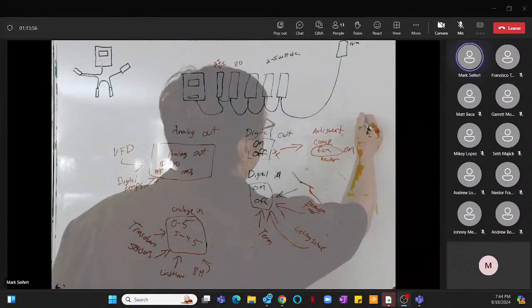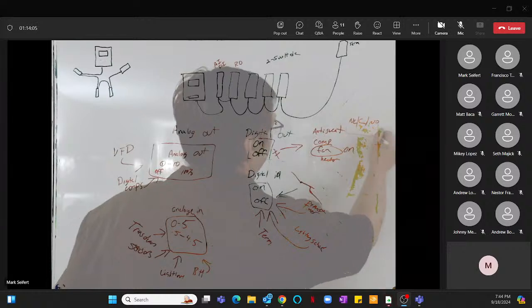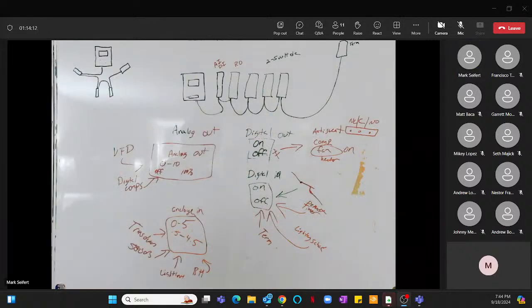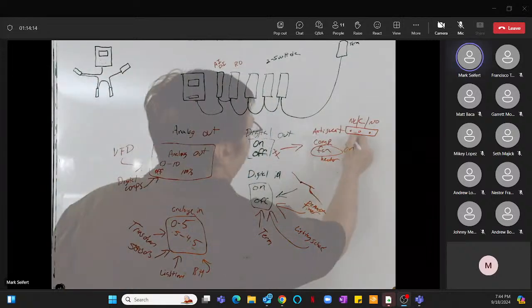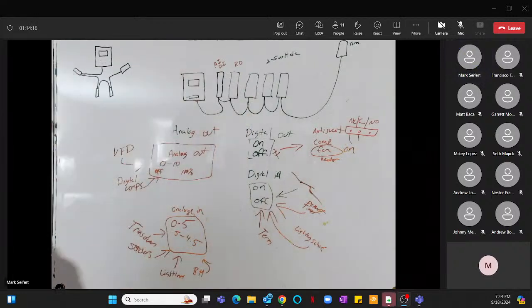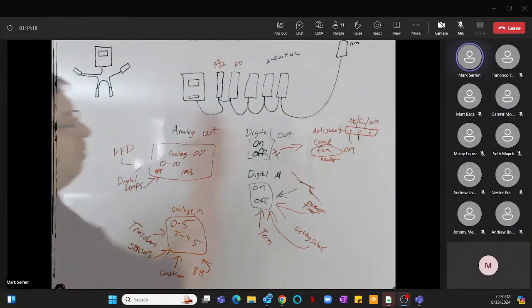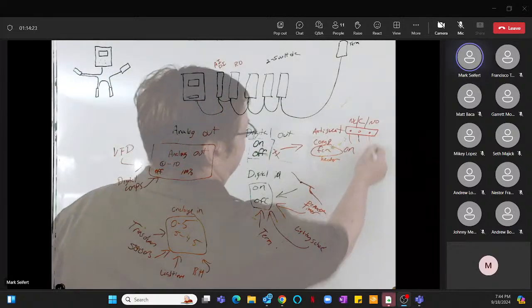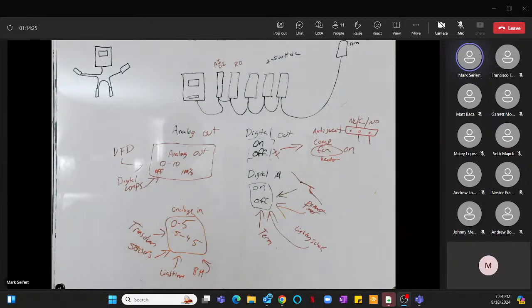On a digital out, you're going to have three: a common, normally closed, normally open. Right? Compressors, always wire to those two, normally closed and common. Defrost heaters, always wired to normally open.